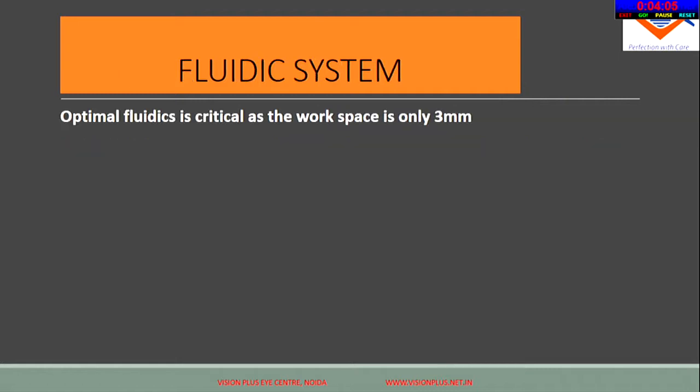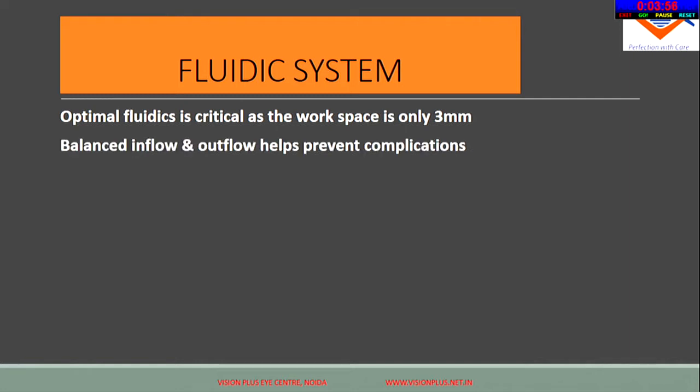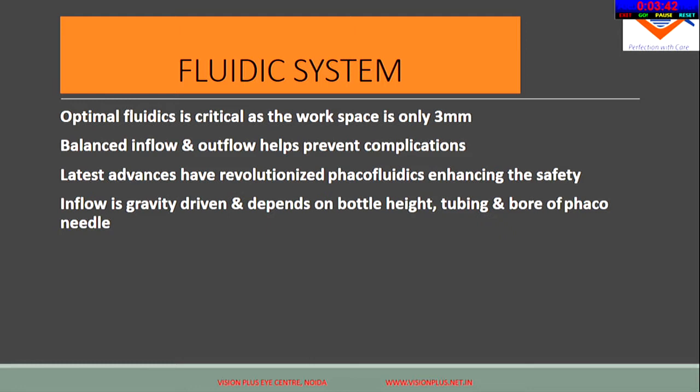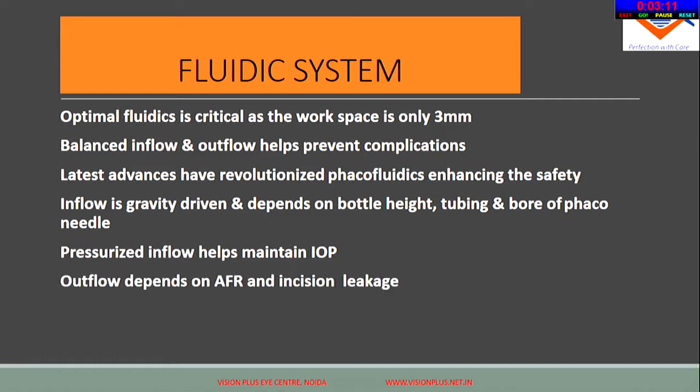The fluidic system is also critical because optimal fluidics are essential — we work in a small space and the balance of inflow and outflow is what prevents complications and maintains chamber stability. Earlier, inflow was always gravity-driven and dependent on bottle height, tubing, and bore of the phaco needle. Now you have pressurized inflow where the BSS bag gets compressed, you can have a target IOP, and thus achieve a much more stable anterior chamber. Outflow depends on aspiration flow rate and incision leakage.